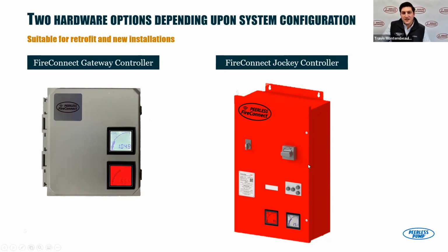What Peerless did, in an effort to simplify the installation and also give retrofit customers a little bit of opportunity for some cost savings and maybe just dipping a toe into the smart connection world, we decided to take all the smarts from the FireConnect gateway controller and integrate them directly into the jockey controller. So giving you a secondary option, or an alternative option, from a hardware standpoint. So we took a standard jockey pump controller that's Modbus enabled, does its normal pressure maintenance. You set the pressure, the start and the stop, and it keeps the pressure up in your system just as it normally would in any type of fire pump system running day in and day out.